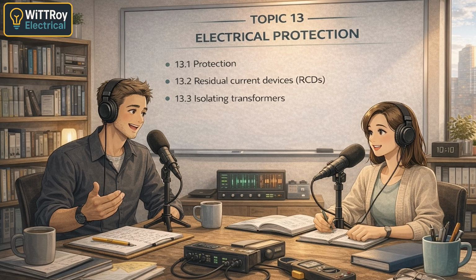Okay. Rewirable fuses provide coarse protection. Because the fuse wire melts slowly. Right. HRC fuses provide close protection. They can interrupt high fault currents safely. Correct. MCBs provide both overload and short circuit protection. Because they have two parts. Exactly. A thermal part and a magnetic part. Thermal for overload. Yes. Magnetic for short circuit.